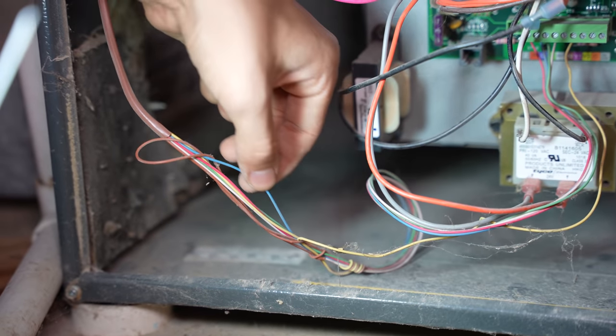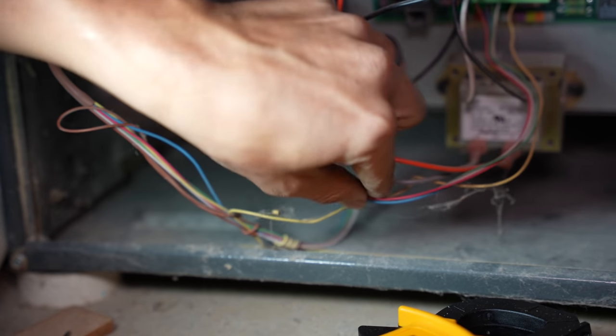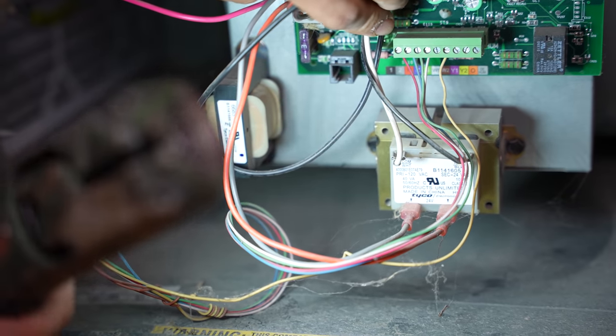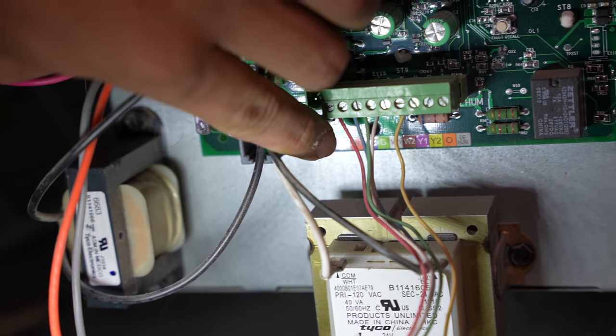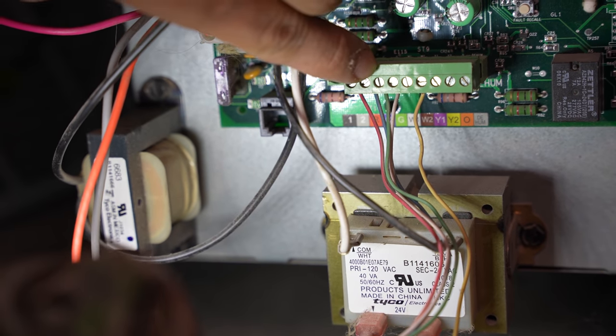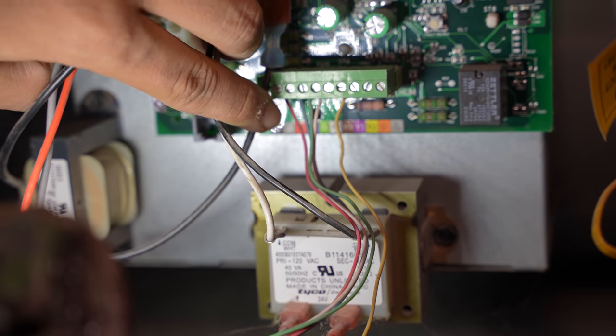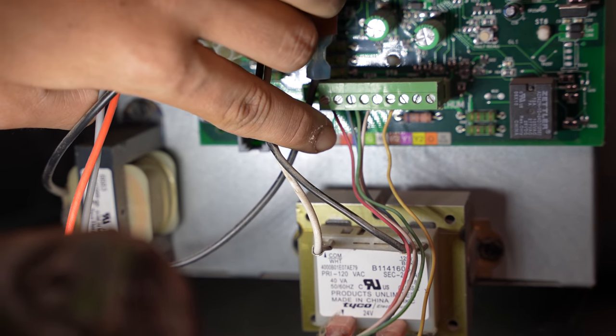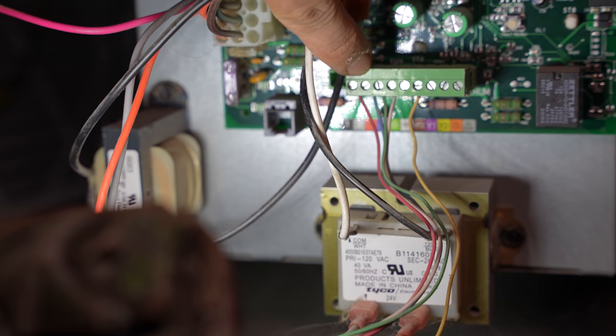So in the case of this furnace, if we follow the blue wire and see where it goes, here it is, and it goes into this terminal strip. As you can see, blue goes into common C right in here under this screw. So in this scenario, the common terminal is going to be right here. So if you're installing something, you would stick the wire into this screw terminal from the bottom there, right over here.